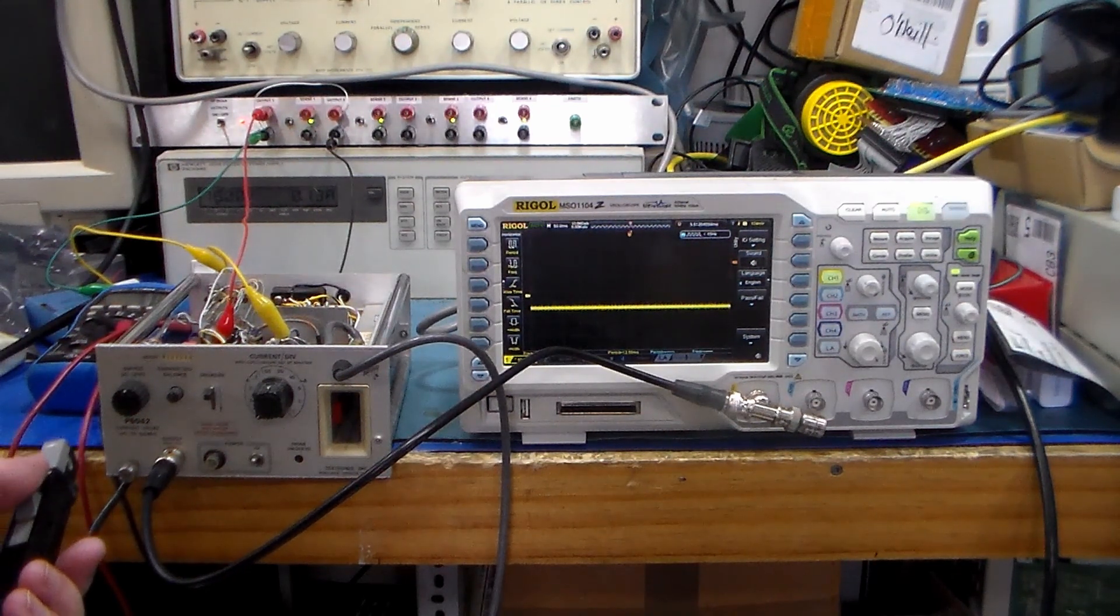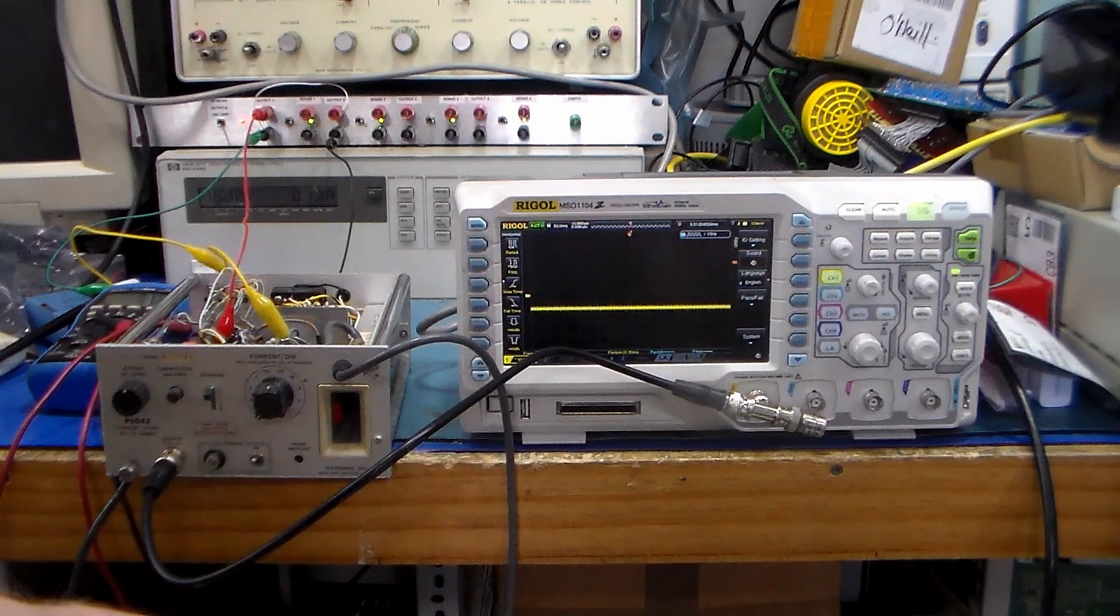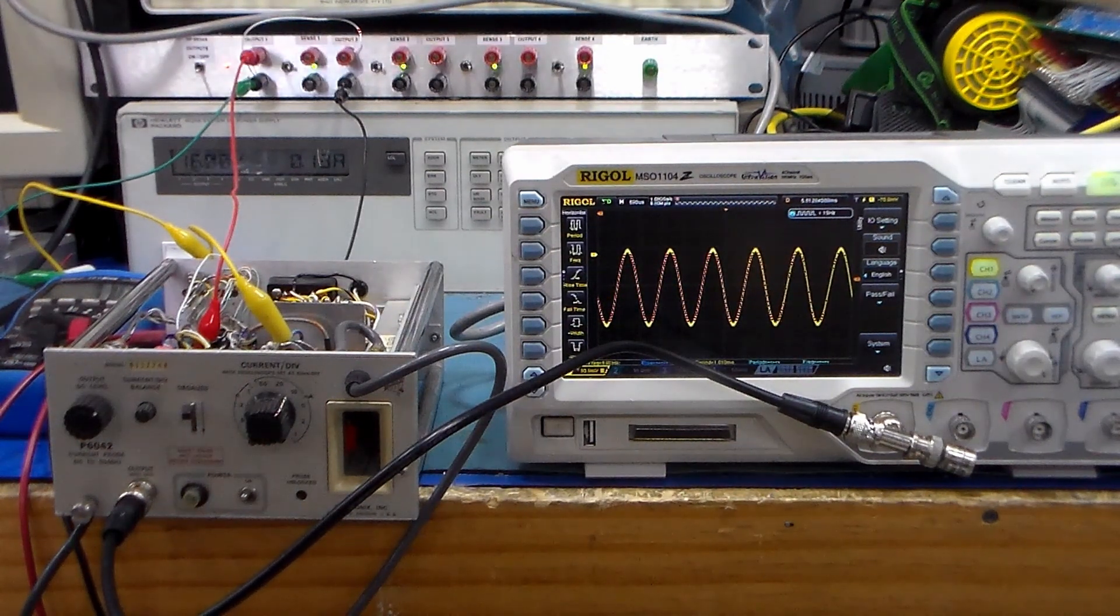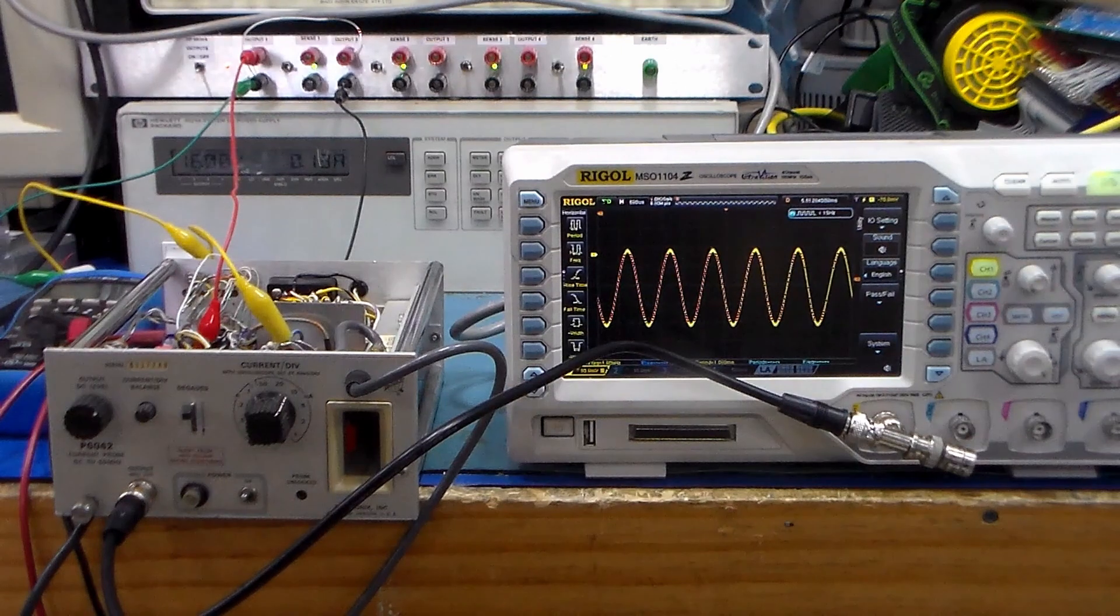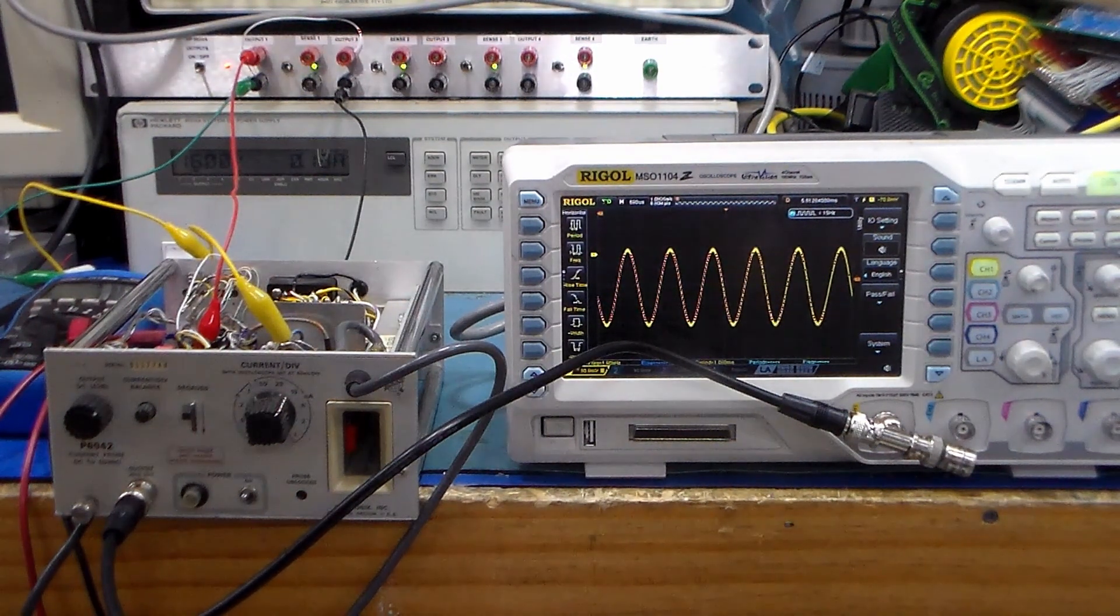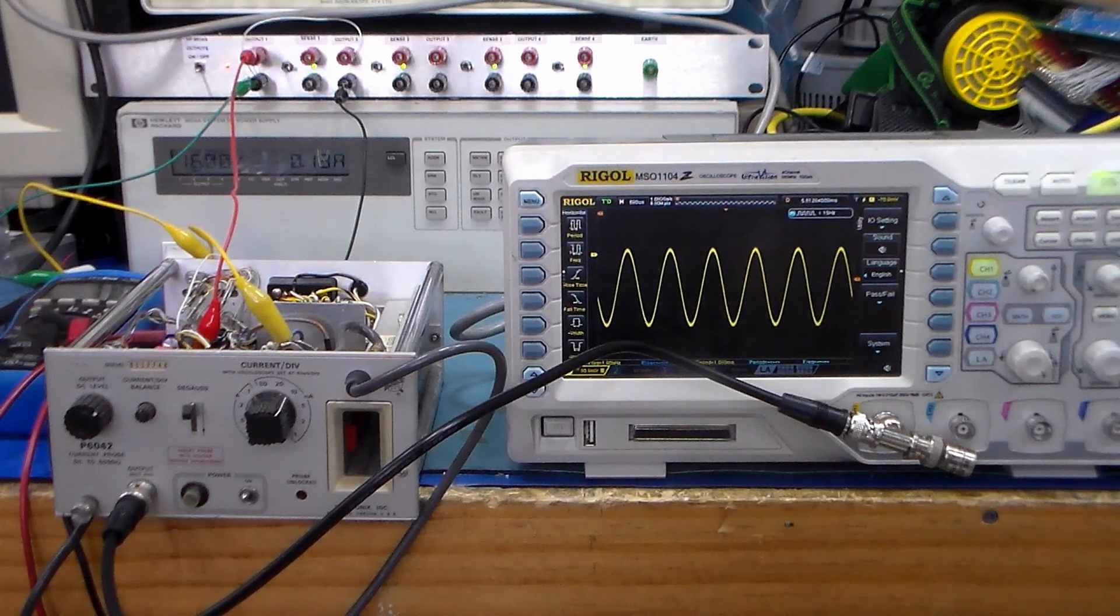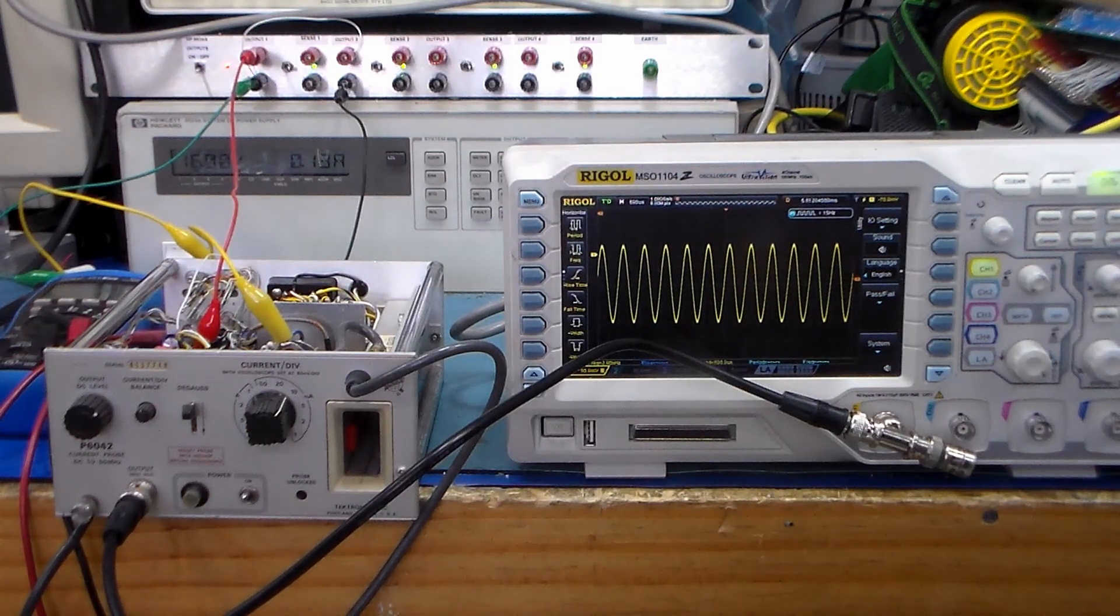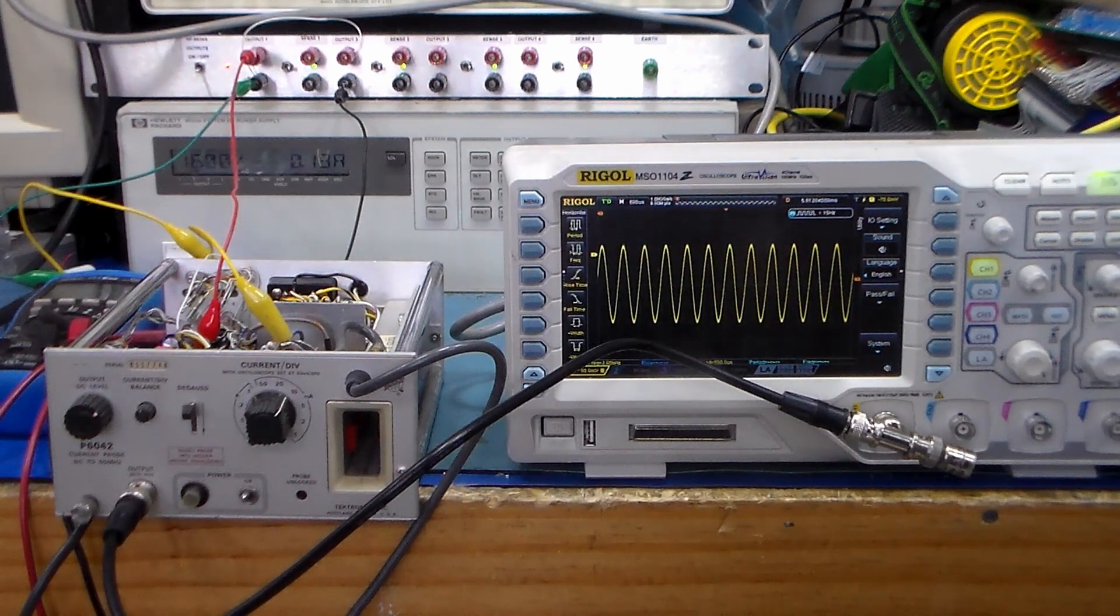The next thing is to actually put a signal into the probe and just see if I can make a measurement. Here I have a 50 ohm terminated line and I'm measuring the current in that line. I haven't actually done any measurements to verify the calibration since the issue with the power supply. We're getting an output and that's a 1kHz signal. In fact if I go over here and change the frequency to say 2kHz, yes, so it appears like the probe circuitry hasn't suffered from power supply failure, but we'll verify that in a calibration once I've repaired the power supply.